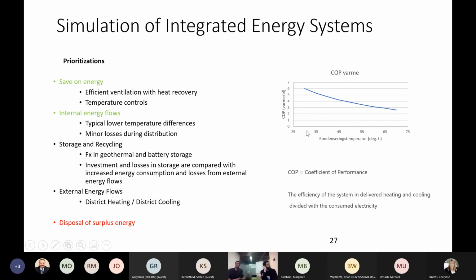When you have very low temperatures, you can operate this heat pump extremely efficiently. But as you go higher in temperature—here we're typically around the hot water temperatures we need to deliver—the efficiency of the system drops. This isn't special to our heat pumps; it's basically the Carnot efficiency of the circuits that governs this trend. So if you can design your heating and cooling systems with the least possible temperature lift, you'll get a much more efficient system.